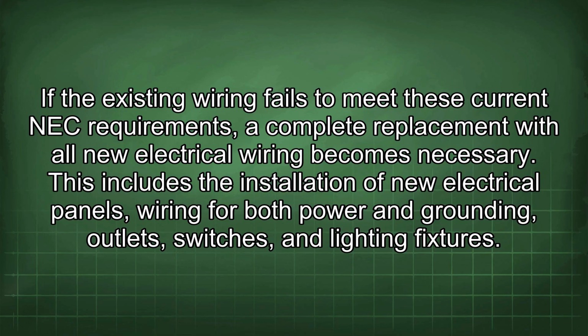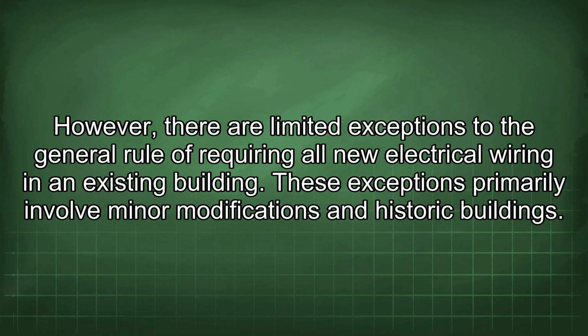If the existing wiring fails to meet these current NEC requirements, a complete replacement with all new electrical wiring becomes necessary. This includes the installation of new electrical panels, wiring for both power and grounding outlets, switches, and lighting fixtures. However, there are limited exceptions to the general rule of requiring all new electrical wiring in an existing building. These exceptions primarily involve minor modifications and historic buildings.